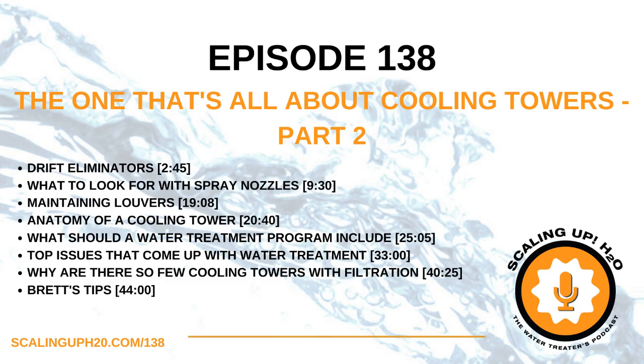I just want to give you a heads up that those riser pipes usually are very low pressure. You might only have 2 to 6 psi of pressure when you are tapping off of that. So depending on how far you're trying to bring that supply water to your water treatment setup, you might have issues getting it back into the basin of the unit. You might require a booster pump depending on the size of the run. So just keep in mind the low pressure of that riser pipe on closed circuit coolers and evaporative condensers.